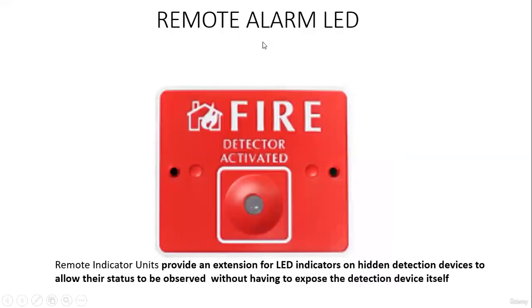Okay. Now this accessory you can see is the remote alarm LED. Remote indicator units provide an extension for LED indicators on hidden detection devices to allow their status to be observed without having to expose the detection device itself. That means this is the remote detector unit, right? The remote alarm LED provides an extension for LED indicators. This is the remote alarm LED, right? Fire detector activated, right? Here you can see the detector activated.